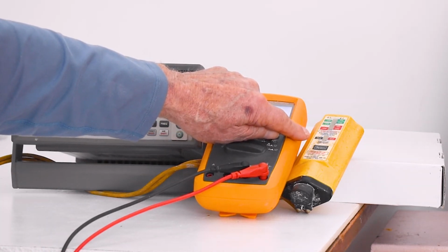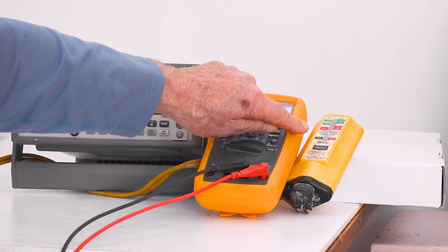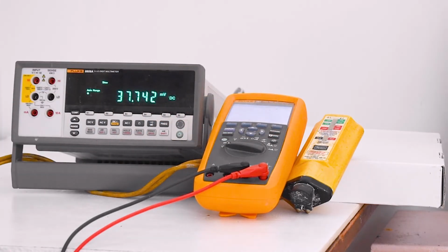This solenoid voltmeter, the so-called wiggy, is a low impedance voltmeter. That is not always a bad thing. It has no batteries because it is powered by the circuit that it measures. When energized, the indicator pops up, showing 120, 240, 480, or 600 volts. The instrument also emits an audible buzzing sound, and it vibrates, which can be felt distinctly. This is great for low light and noisy locations.